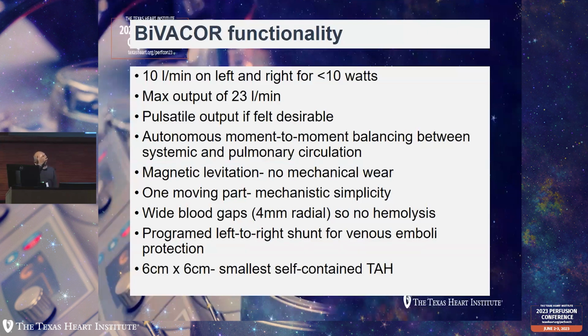So at the time, you had 10 liters per minute flow left and right for less than 10 watts. You could go up to 23 liters per minute if you wanted to. Pulsatile, if you wanted, you can make it pulsatile. Autonomous moment-to-moment balancing between the systemic and the pulmonary circulation. Magnetic levitation, no mechanical wear, there's no bearing, there's no other moving part besides the impeller itself. It's just one moving part. Wide blood gaps, like I said, the area around the impeller is about 4 millimeter radius, which gives you continuous wash from left to right, because the left is working at a higher pressure, higher afterload than the right. So you always have this left to right shunt all the time, which is going to keep cleaning the surrounding area.